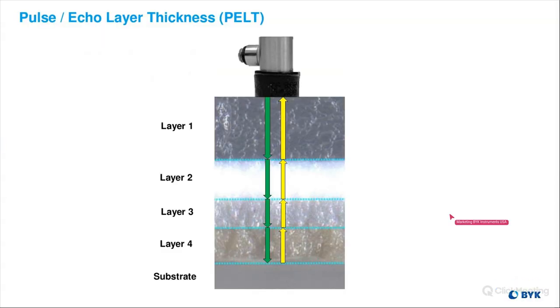Okay, yep. I can definitely talk to that point. So the glycerin, we put a small drop of glycerin in the cap of the transducer, and that's to let the sound penetrate through the cap material, and then it should only have to be applied maybe once a week or once a month. For maintenance purposes, go in with a lint-free cloth and clean out the inside of the cap and the surface of that transducer. We want you to use as minimal an amount of glycerin as possible, because as we know, in a paint shop, glycerin is a no-no, right? Yeah. I mean, of course, we are taking measurements on finished surfaces, so not in between. So it's not necessarily that big of an evil. But then we use water on the surface, and you would want to have a spray bottle or a dropper with you next to your gauge, so you can prep the surface.